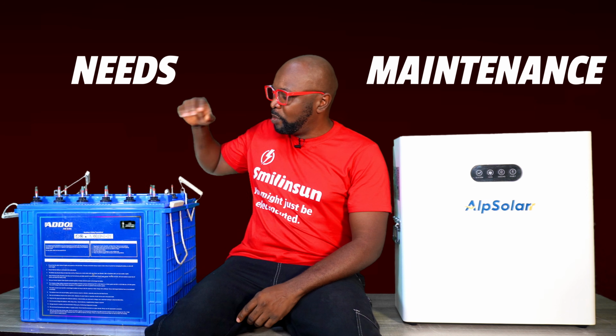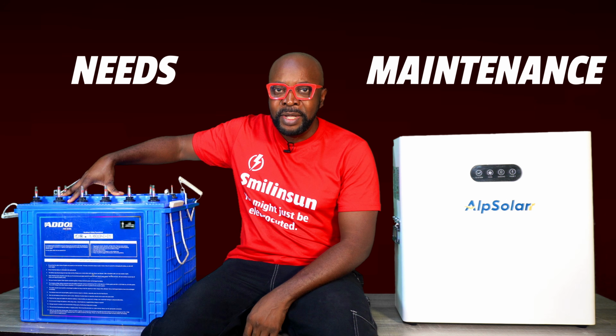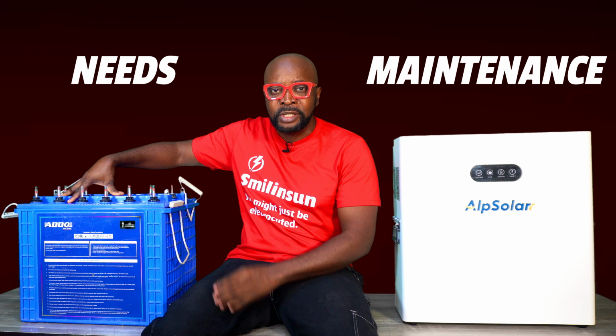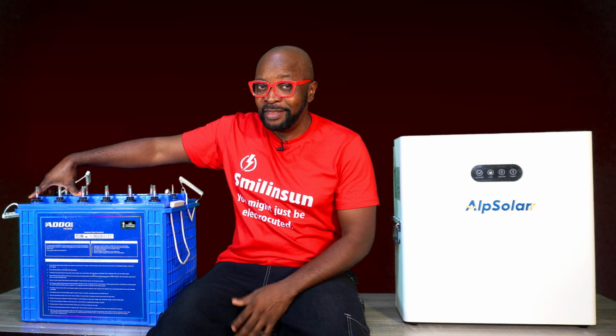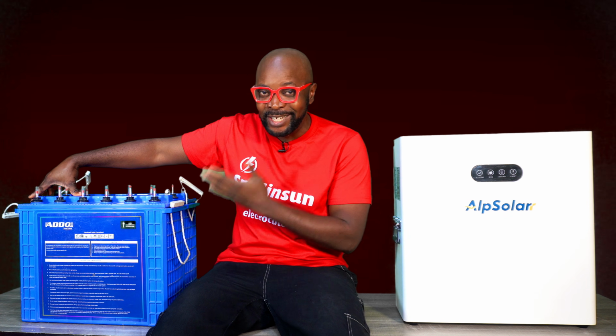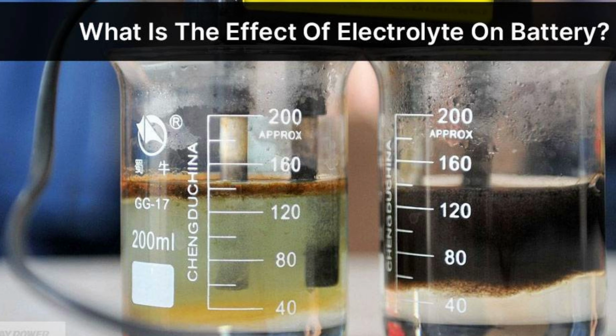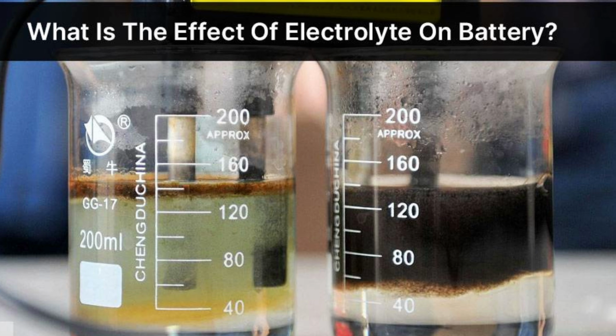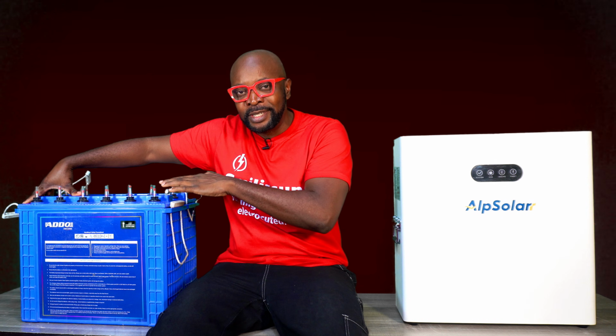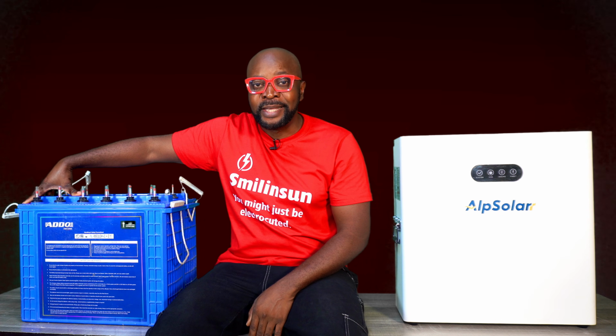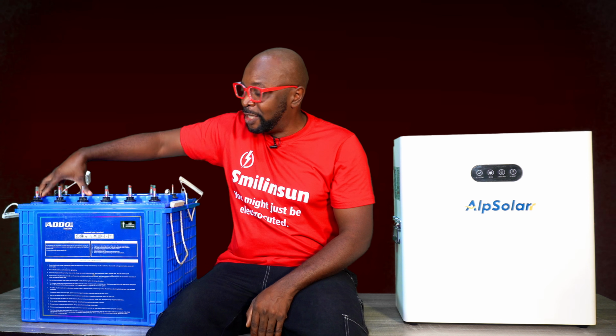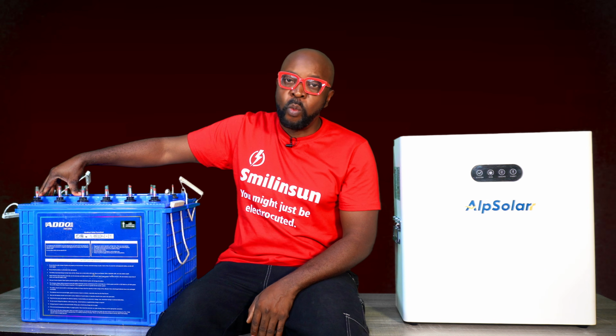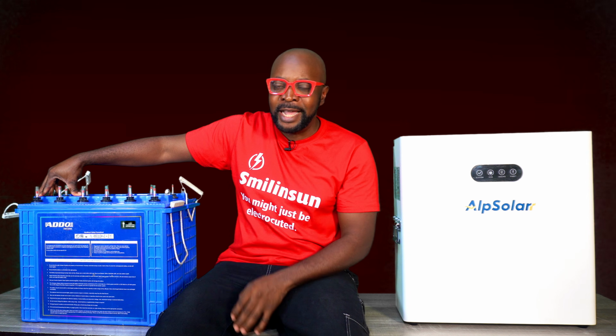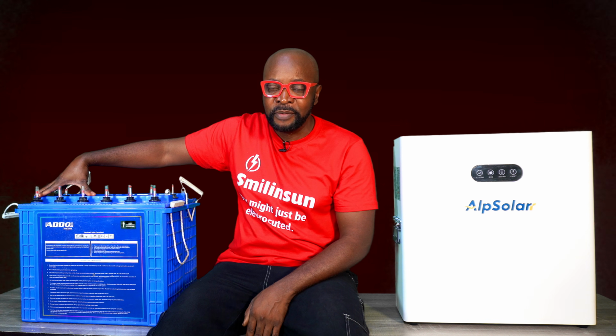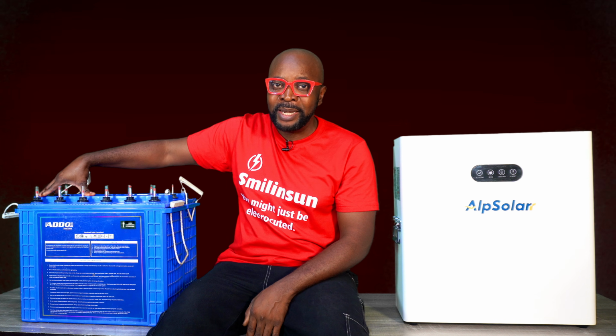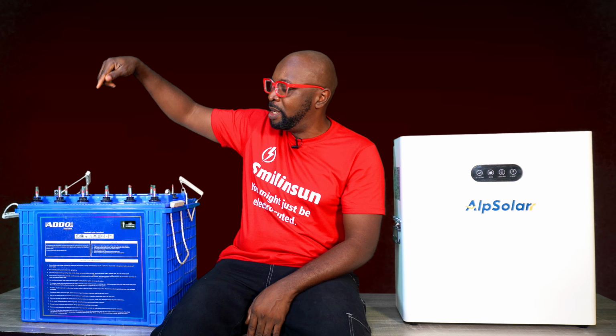Number 1, when the batteries are charging, it emits hydrogen. Of course, you know that the content of the battery is electrolyte, not electrolyte in the body. Electrolyte is a mixture of sulfuric acid and distilled water brought to a certain concentration, referred to as specific gravity. That's what you have on this battery. But when the battery is charging, it emits hydrogen. The battery loses water. Okay, so at some point you might need to hydrate the battery by pouring in water.